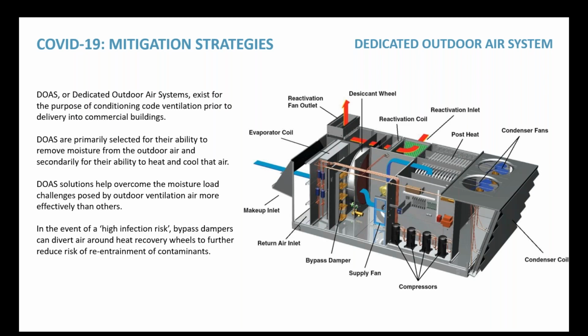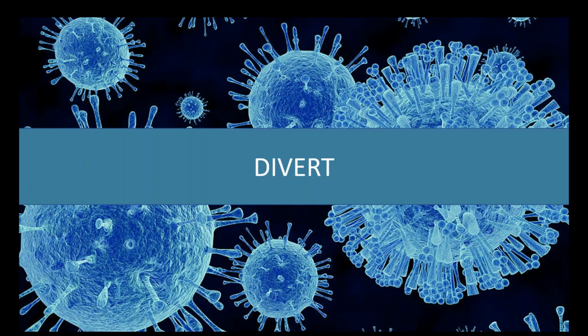But in the terms that we're dealing with now, which is an epidemic conditions type scenario, you have to look at these wheels because in some cases they do bypass air from the exhaust airstream to the supply airstream. So we have been recommending in some cases that you turn the wheel off and only operate it when the system can no longer deliver the supply air set point temperature and humidity, because we don't want to unnecessarily burden the comfort conditions in the space by delivering extremely hot or extremely humid air. But at off-peak design, you may not need to operate that wheel, and you can still supply the amount of air you need at the temperature and humidity that you need. And so you eliminate the potential for that cross-contamination.